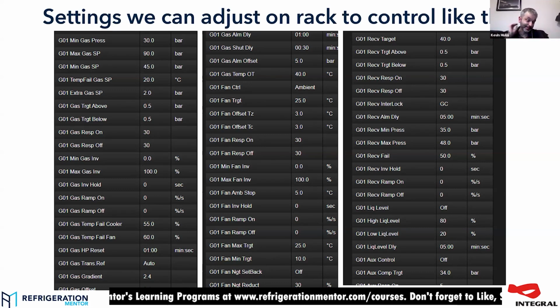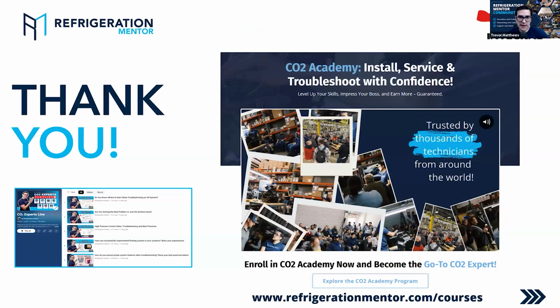And there are a lot of different ways you can control that, but be sure what's causing it before you start fiddling with them all, as you said earlier. Yeah. And I think that is the big thing too, understand the system that you're working on, because we want everything to be flatlined, but it's not always that way. You've got defrost, coils are going to freeze up, customers not cleaning out the coils, people dropping stuff into drains. You don't want to be changing parameters if you don't know if the coils are clean, if all the fans are working, if the airflow is good. You can't be changing these parameters we're talking about without doing all the basics first.